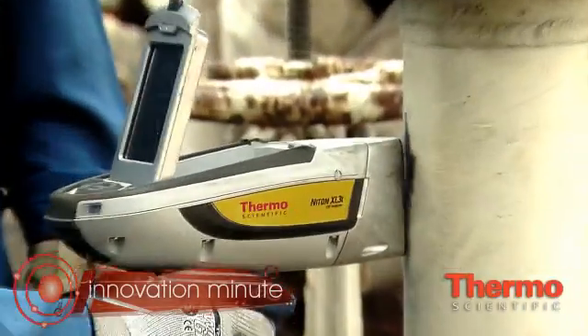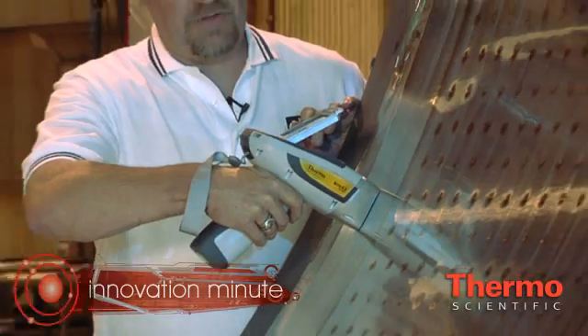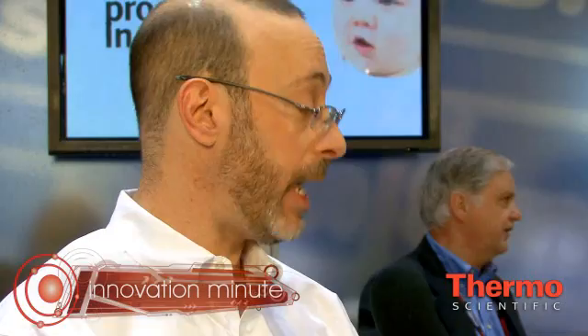For market applications such as metal alloy analysis, we can now do trace and tramp level analysis. It also gives us the ability to analyze light elements in an air path — so no longer is a vacuum or a helium purge required to see magnesium, aluminum, or silicon. We can also see sulfur in stainless steels, which gives us the ability to sort free machining stainless steels from other stainless steels — very important in the manufacturing segment.